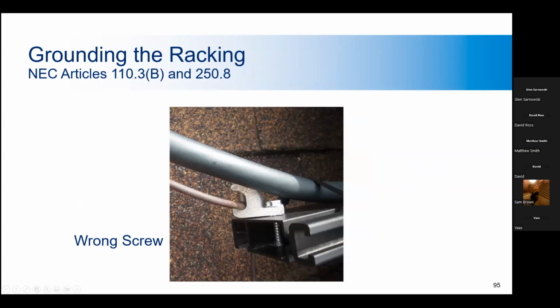Here's a situation where the bonding to the rails was accomplished through a self-tapping screw, and this would actually fail. The reason is that the lug or the screw used is not rated for bonding purposes. You typically need a fine threaded machine screw that has a minimum of two threads in contact with the metal. This had too coarse of a thread, so this would fail code for that reason.